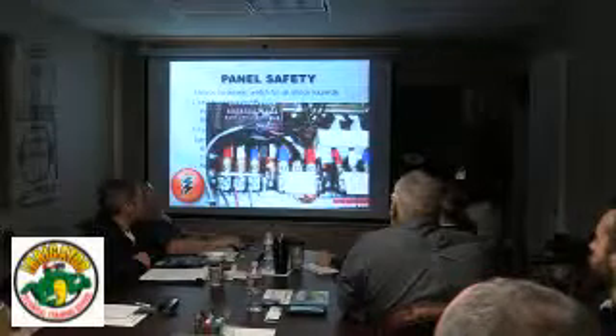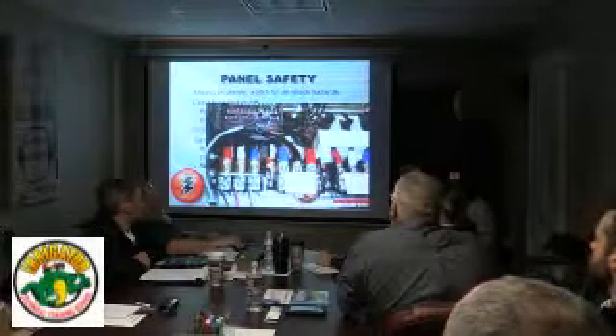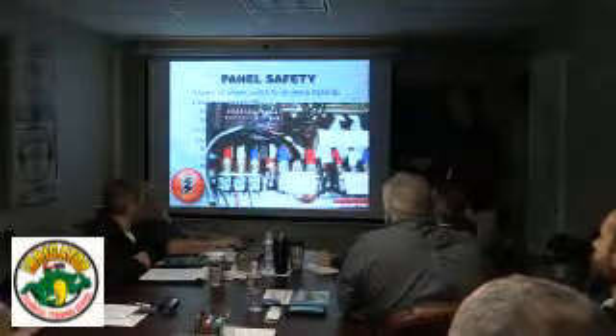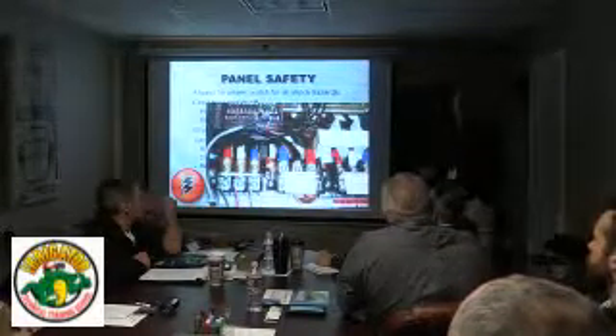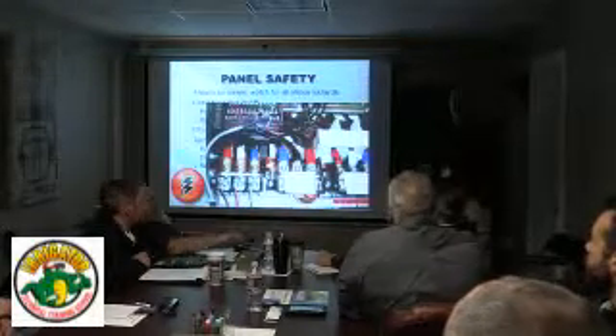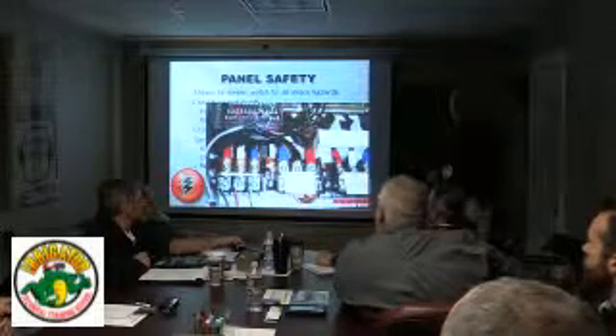And on a 480 volt drive like this, you put your meter in DC volts, measure across here, you could measure as high as 700 volts. So on some of the larger Mitsubishi drives, it can take up to 4 or 5 minutes for that to go down. So if you do have to work on a larger Mitsubishi drive like this, put your meter in DC volts, measure this, wait for it to come down to a safe level, 50 volts or less.